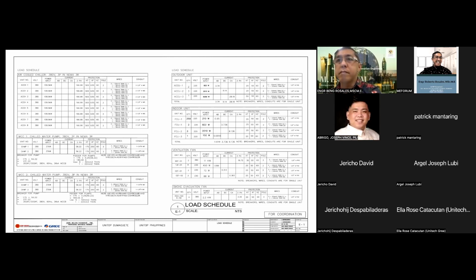Actually, according sa PEC, 10 times the original current yung starting current. Pag hindi niyo kinompensate yon, the possibility na mag-trip yung breaker ninyo ay mataas. Most probably mag-trip siya. Hindi pa nagsisimula yung makina ninyo, trip na agad yung breaker. Why? Kasi hindi na-compensate yung starting at inrush current.